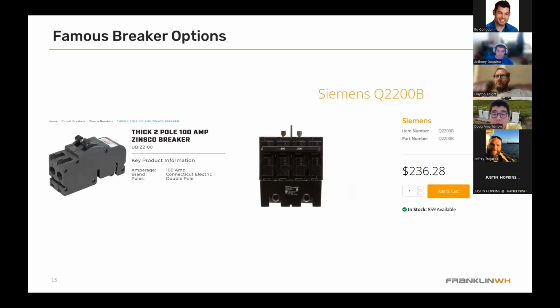You should definitely allocate some budget for these specialized breakers if you're going to do main panel upgrade avoidance. It's not every day that you see this kind of 4-pole 200 amp breaker, where the 4 poles span and contribute 200 amps out of that 100 amp or 200 amp service. Those Zinscos are also notoriously bad panels, but there are solutions with 100 amp service breakers there. And this is important, guys.